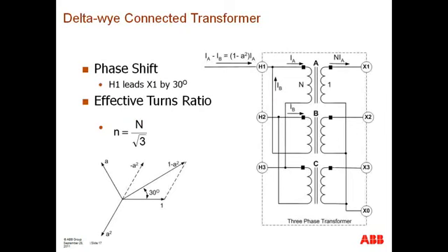Okay. Here we have a similar arrangement, but now the delta connection sits on the high voltage winding. So in this particular case, it's not phase A connected to the non-polarity leg of phase C, but we actually have phase A connected to non-polarity of phase B. We have phase B connected with non-polarity of phase C, and then phase C connected to non-polarity of phase A. And this is what's known as an A minus B delta, which in turn results in a connection where this winding will lead the low voltage winding, or the Y connected winding, by 30 degrees.